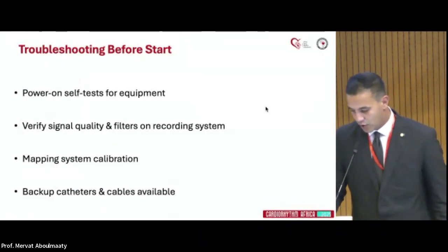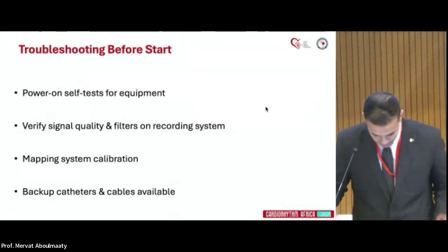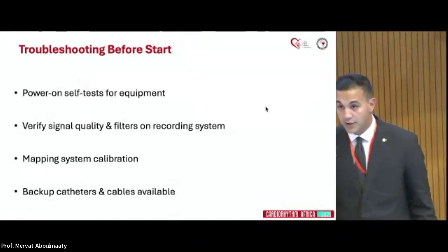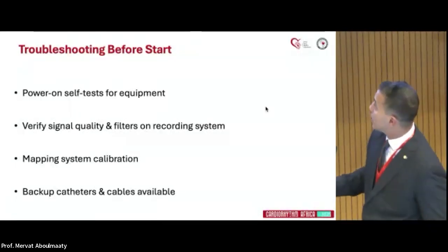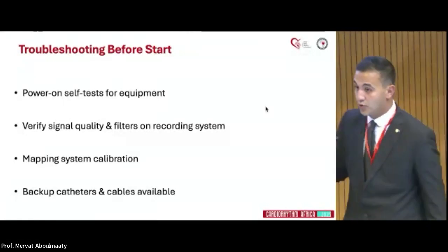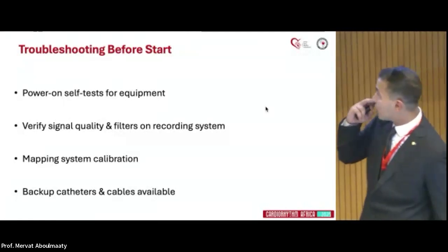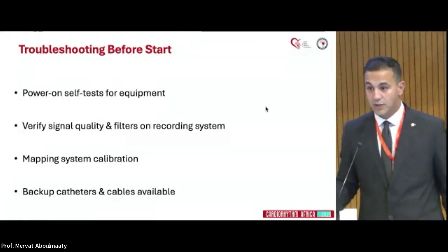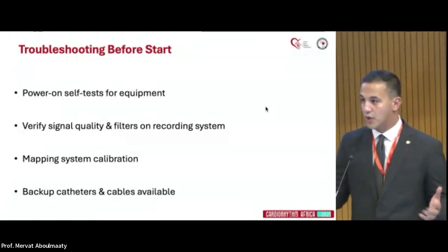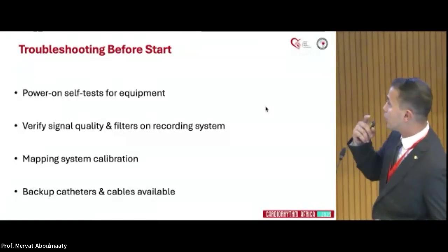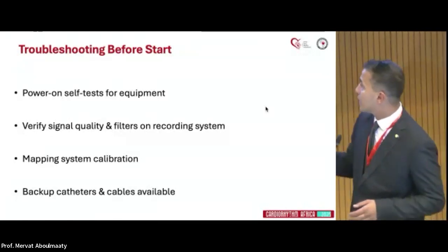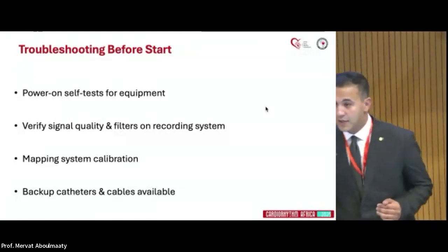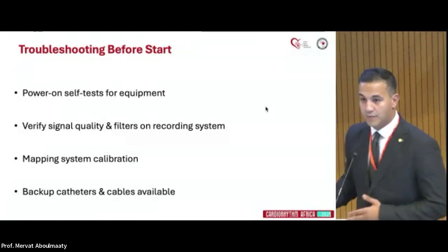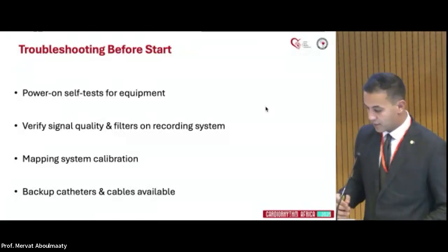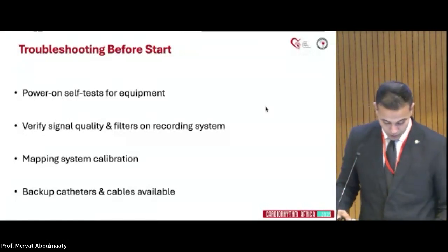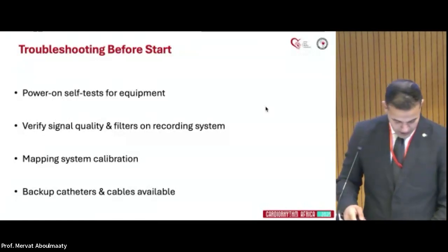So we do the power-on self tests for all the equipment. Then we verify that the signals and the quality of the signal and filters on the recording system are all good and set. Then we go for the mapping system. We do the calibrations, if there are patches, if we want to connect the patient. This is very important also. Then we go for the backup catheters and cables and make sure that we have the backup. If anything faces us throughout the case, we'll be ready.